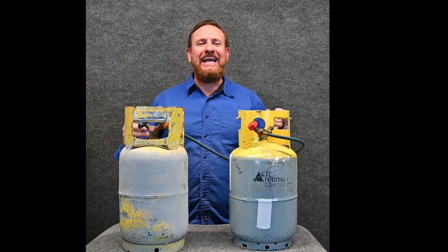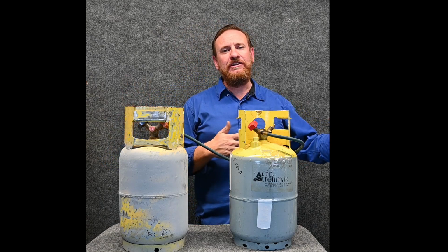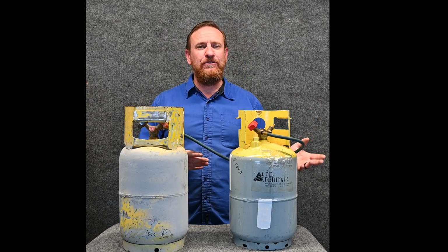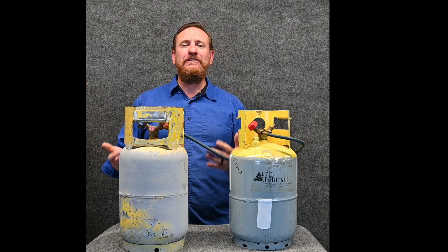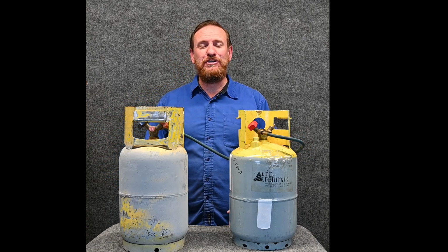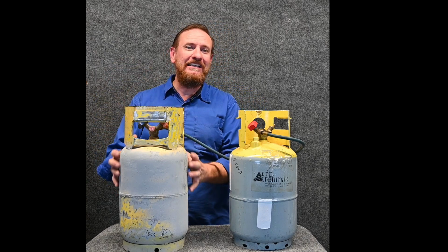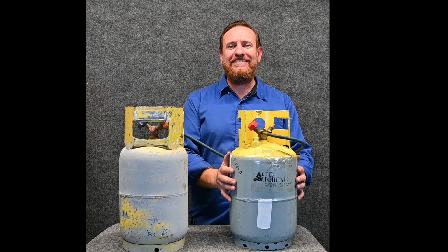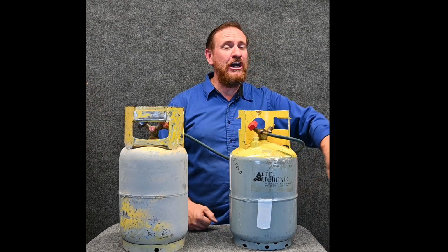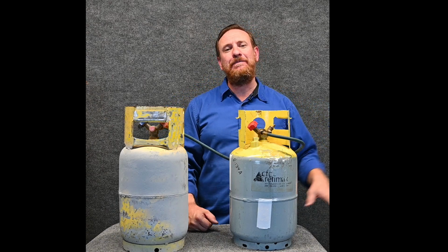I thought, great, I can save time. I can have it pulling all of these. It's going to take a good part of the day to do that. I can go do something else. Well, I went to lunch. When I came back from lunch, what I found was really surprising. This tank was completely full of refrigerant, and this tank had a lot of refrigerant in it, and the others were almost completely empty, only vapor alone.